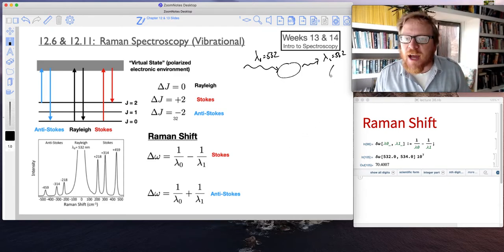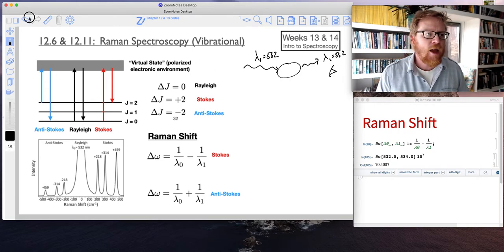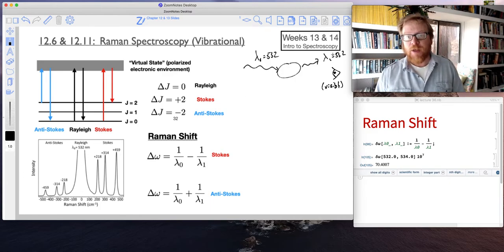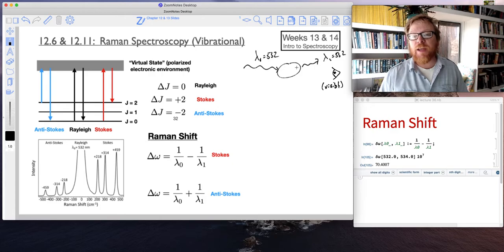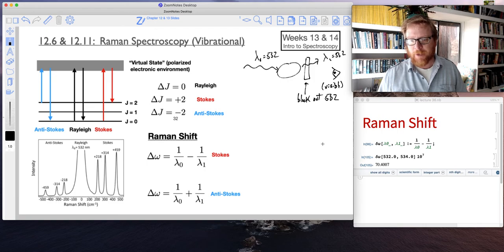And what I also want to point out, I'm going to draw our little detector here, okay? And our detector is detecting visible radiation. It is looking for that 532 or thereabouts wavelength, all right? So as you can see, that 532 peak blows out this scale. So typically you would use a filter to block out the 532 wavelength. So block out 532, okay?